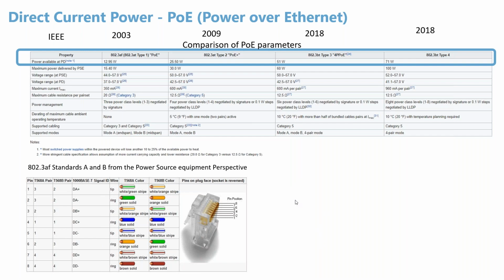The power over Ethernet is delivered over category 5 or better cable to a maximum distance of 328 feet. So you have a better opportunity to use these cables for longer distances without worrying much about the voltage drop. PoE installation reduces materials and labor costs by using a single Cat 5 or 6 or better connection for power and communication. This greatly simplifies the installation process, saving time and minimizing safety risk. Next slide, please.